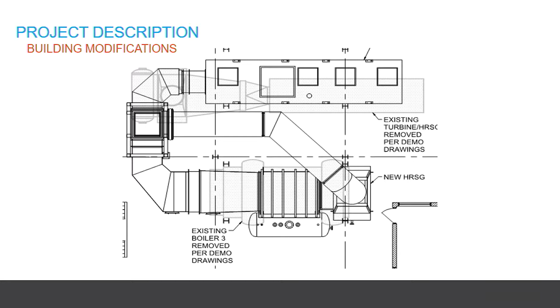This gives us an idea of the layout inside the building. At the top of the image we see the whole previous lineup, with the CT faded back in the line work - that's the CT and HRSG. The new CT was large enough it almost took up that whole space. At the bottom of the image, boiler 3 was removed and the new HRSG was put in its place. Tracking through this image, the hot gas exits the far left of the page, goes up and down through the HRSG where the stack is, then that angled duct works back to the center of the page. It's a pretty unique arrangement - probably won't see many arrangements like that.